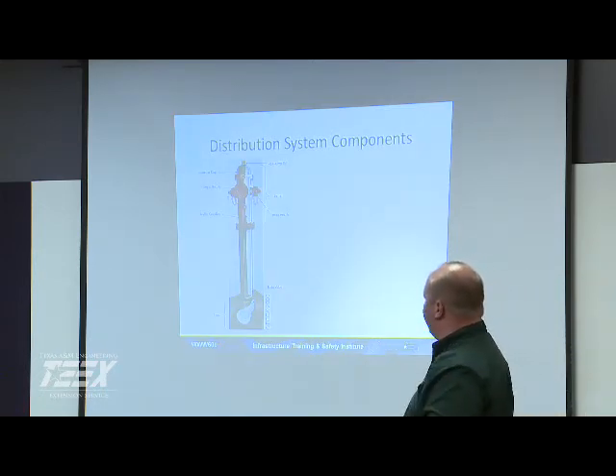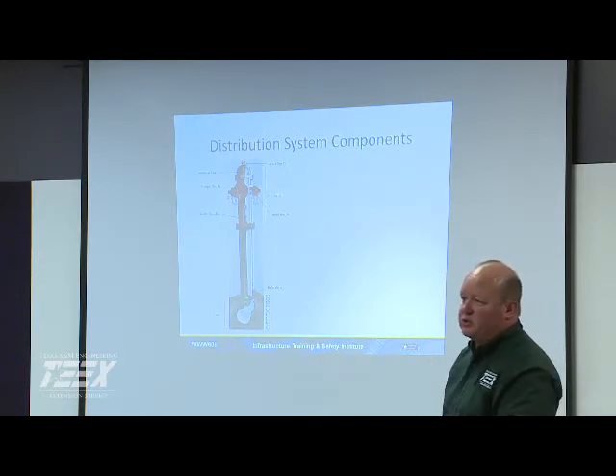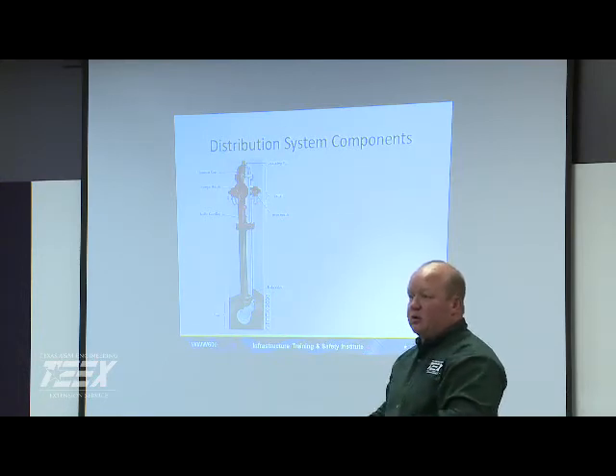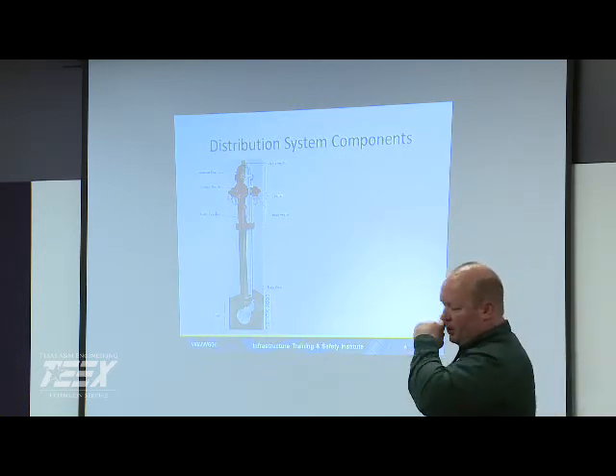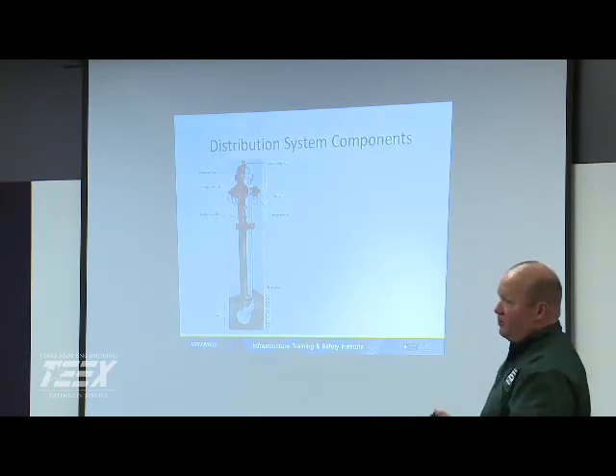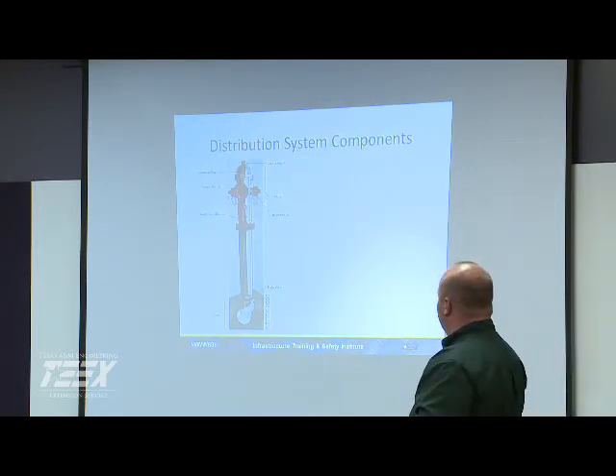Yeah. Okay. Talked a little bit about fire hydrants. One of the big things now is the traffic controlling breakaways. Have you all upgraded into those? The breakaways? Yeah, all the large breakaways. Okay. Dry barrel, especially in the cold weather. It's coming out in California where they still have a wet barrel, but I don't know what the purpose of that is, other than it was easier to work on the valves because everything's up on top. Yeah. But any kind of cold climate, you've got to have a dry barrel.